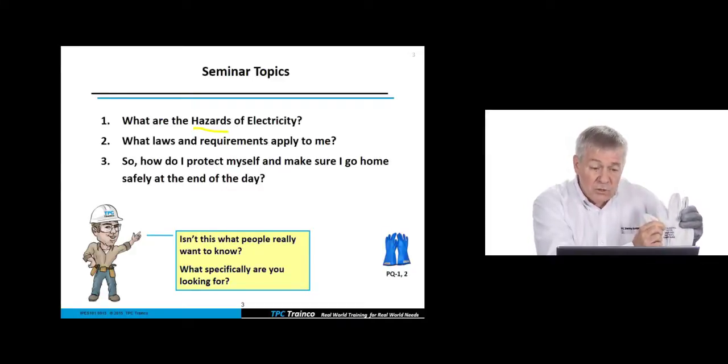I have another question, and this question is from Robert. He wants to know what the 22 calories really means. Well, that's an indication of how much heat that this leather protector will protect me against before I receive a third degree burn. And we're going to talk in detail about calories per centimeter squared and incident energy when we discuss our arc flash analysis a little bit later in this class.